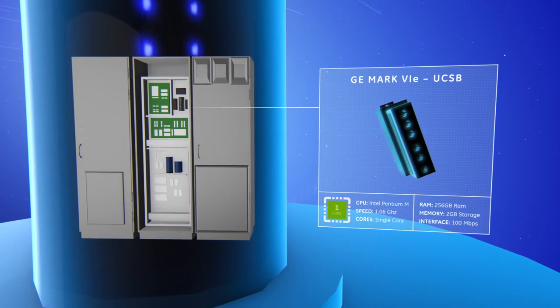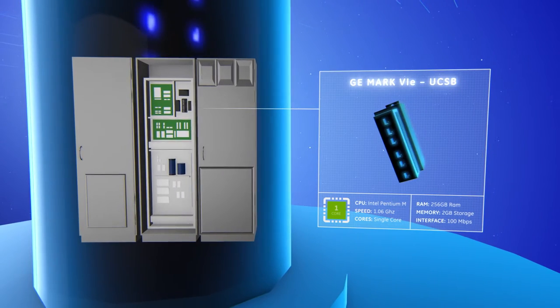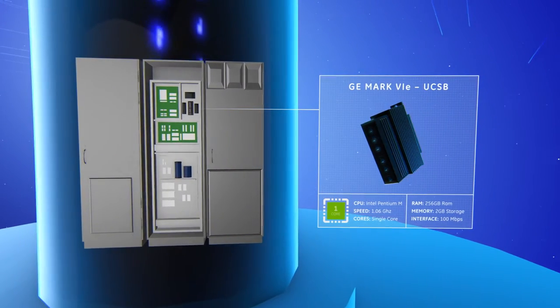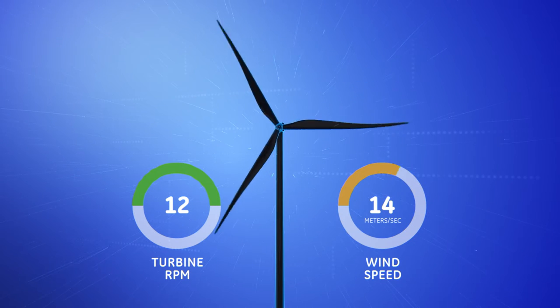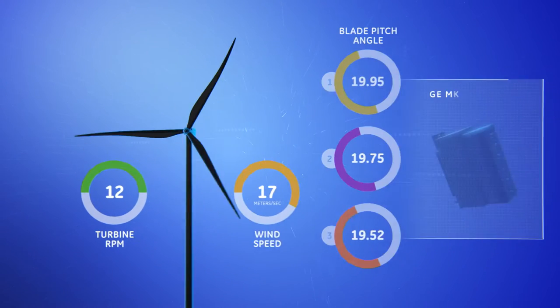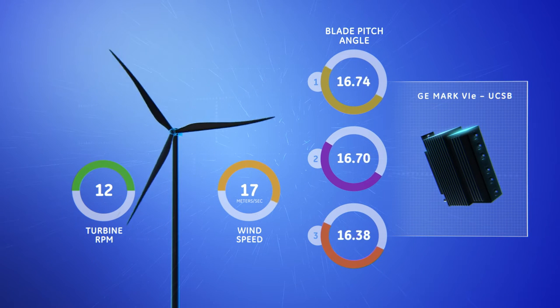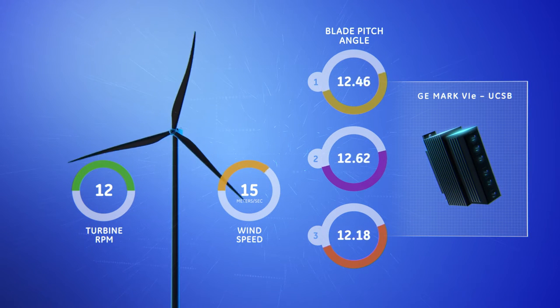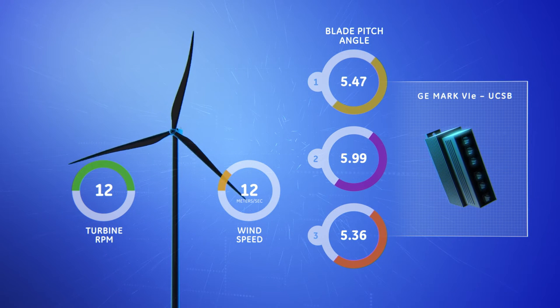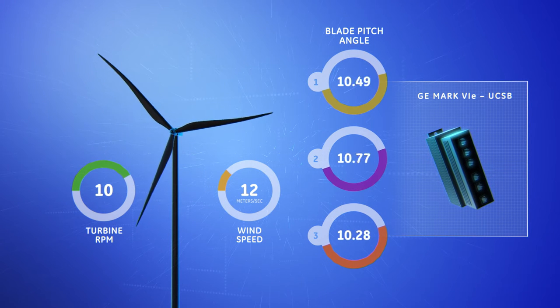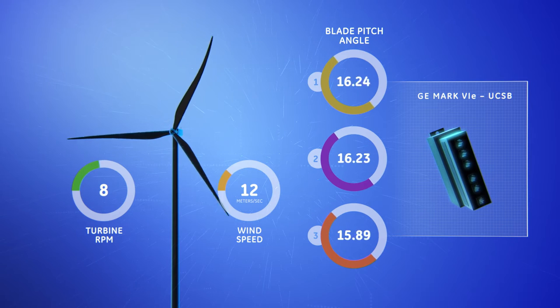One task of the controller, which could be GE's Mark 6E solution, is ensuring that the wind turbine rotates at a constant speed despite turbulent variations in the wind. To do that, the wind turbine controller uses the measured signals to compute the pitch angles of the blades. Increasing or decreasing the pitch angle causes the blades to capture more or less energy from the wind, so the rotor goes faster or slower.